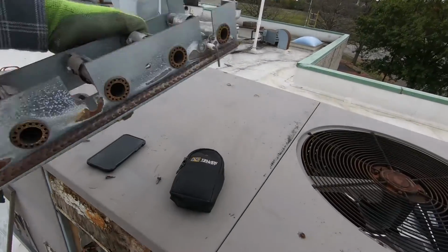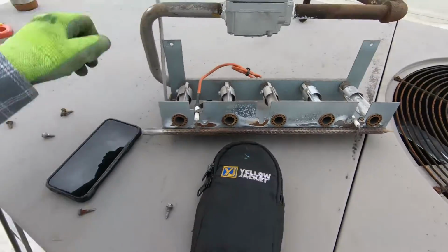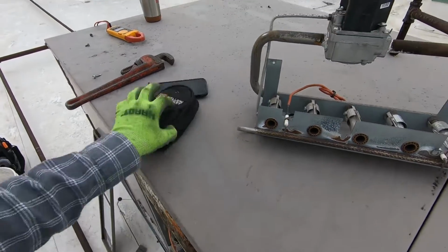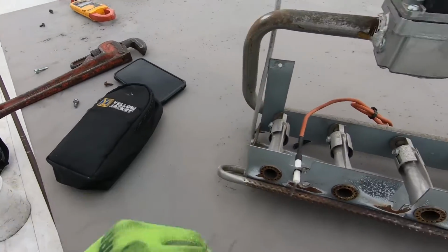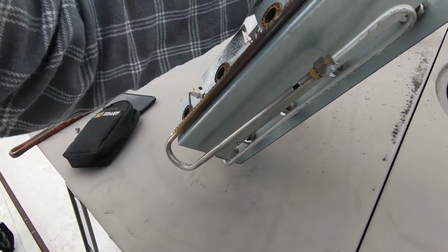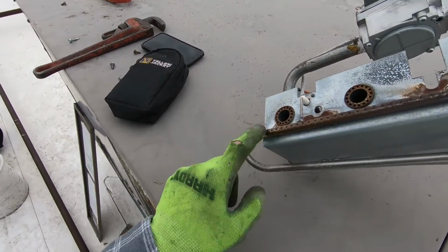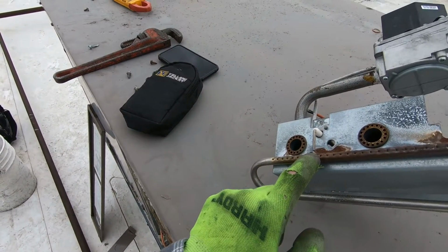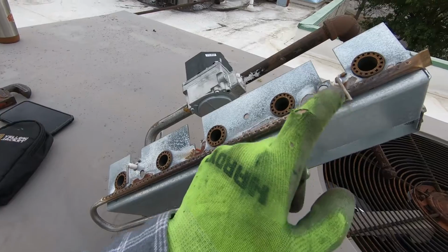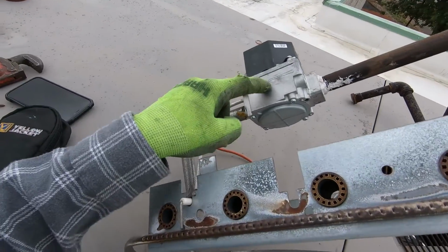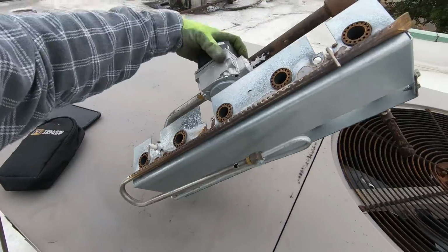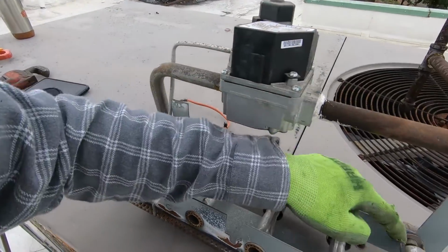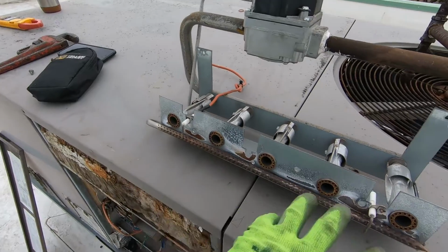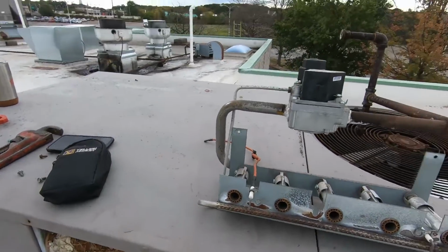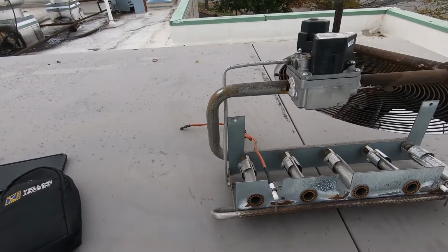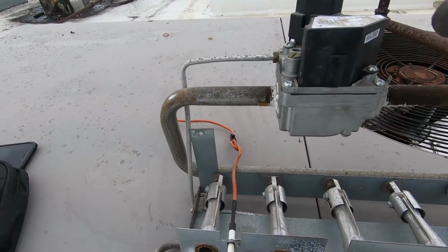All right, guys, got the whole thing pulled out here. And as you can see, we've got a pilot tubing that feeds down over and around to an orifice through this carryover tube. And all that does is it ignites here, and then it proves flame here. And once the flame is proven, then the main valve on the gas valve opens, and you get your gas delivered through the manifold, through the orifices, through the burners, and they all light off of this pilot, this carryover tube that was fed by this pilot tubing here. That's PV on your gas valve, and then MV on your main burner.